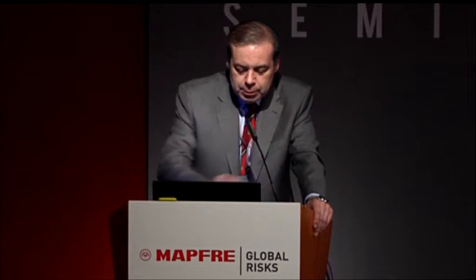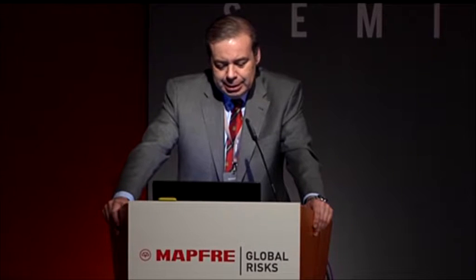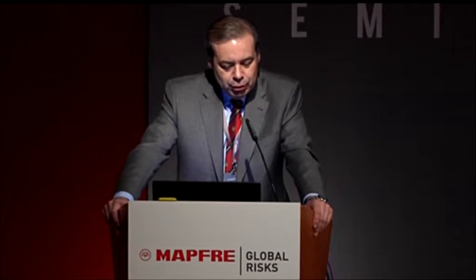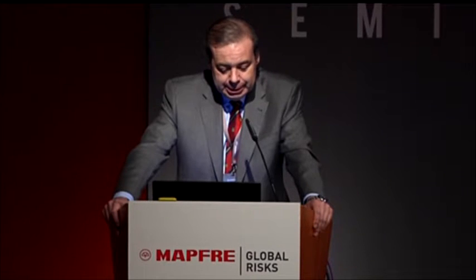The main causes of degradation in gas turbines are fatigue phenomena, both low cycle and high cycle, i.e. thermal origin tensions produced during startup. Then we also have high cycle fatigue, stress corrosion cracking. We've also identified erosion corrosion phenomena and the weakening of material, or fretting.